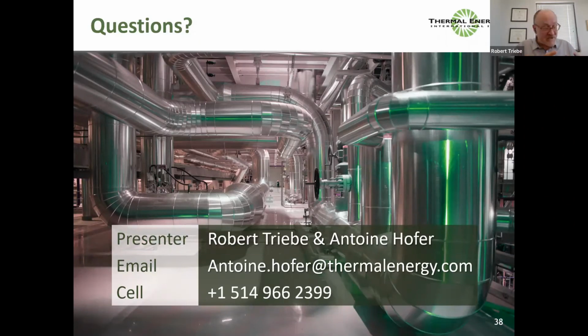But again, once you get to small institutions and commercial, the custom engineering element becomes a relatively large fixed cost, which smaller projects often can't support. So I don't want to trash catalog engineering, because if people don't want to pay for engineering, well, then catalog engineering is the way to go. Yeah. Well, but you get what you pay for. Absolutely. And in our cases, these systems, and I'm talking large systems, hundreds of thousands, even 1 million CFM affected, that we convert steam coils to low temperature glycol and have massively efficient boiler plants in big industrial facilities.